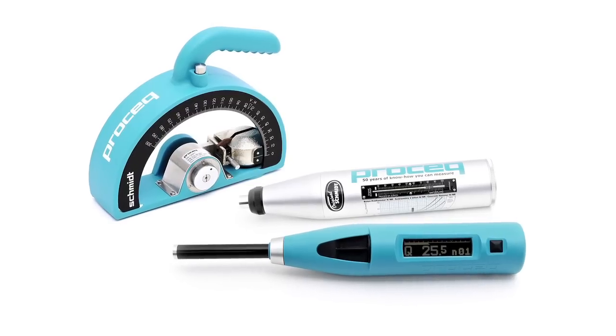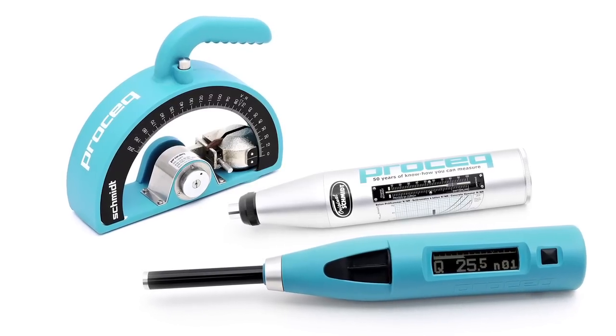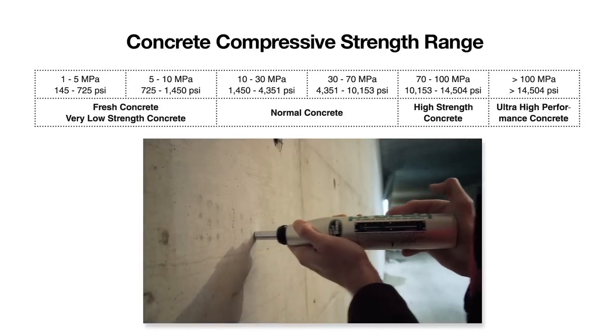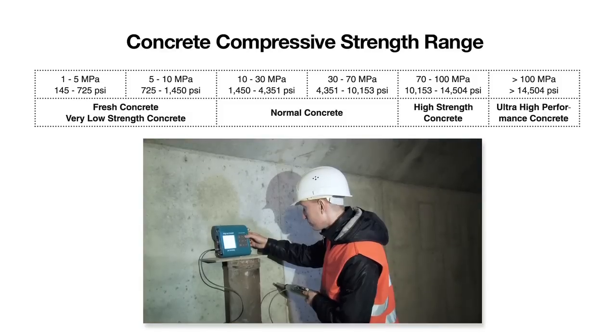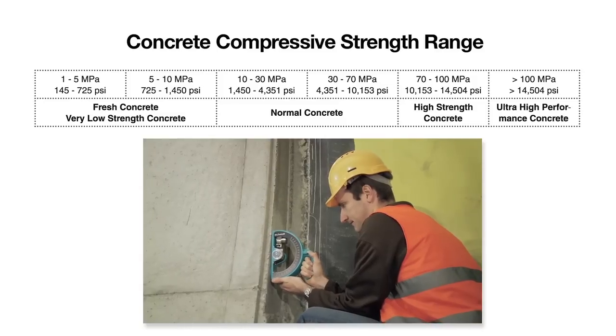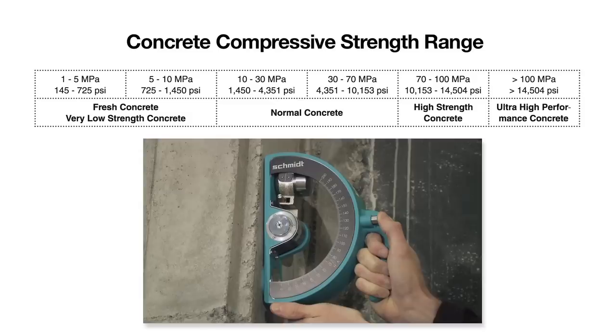Proceq's Schmidt family of concrete test hammers is the most comprehensive portfolio available. It covers the entire range of compressive strength classes from 1 MPa to over 100 MPa (14,504 PSI). Each rebound hammer is designed to meet the specific needs of the customer, with both standard impact energy and low impact energy versions for thin structural elements and brittle objects.